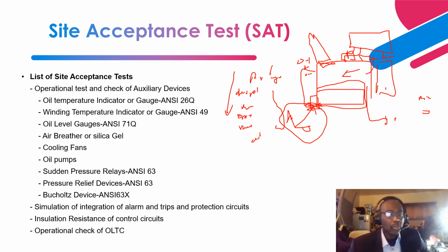So what you do is plan for the installation of the transformer. During installation, they install the transformer and all the components. We took an example of a free breathing transformer, a transformer with a conservator tank. There are two types: we have the sealed type and the free breathing. The sealed type is basically where on top of the oil, you have a nitrogen blanket, creating a positive pressure on the oil, right?